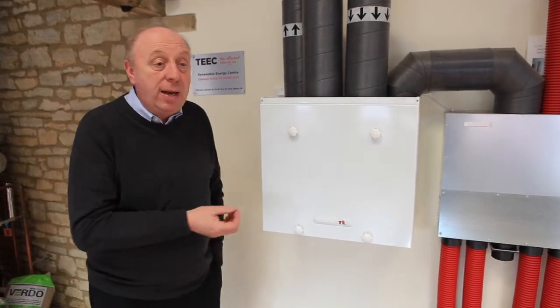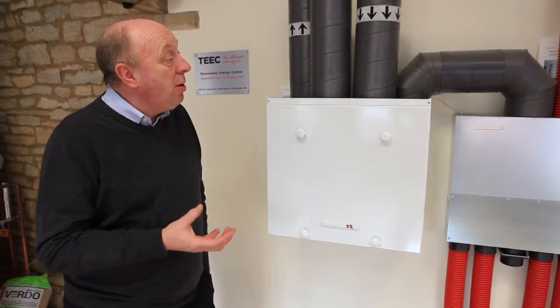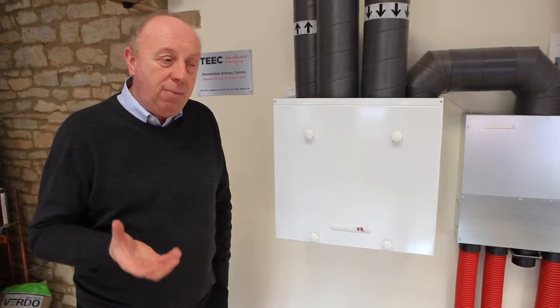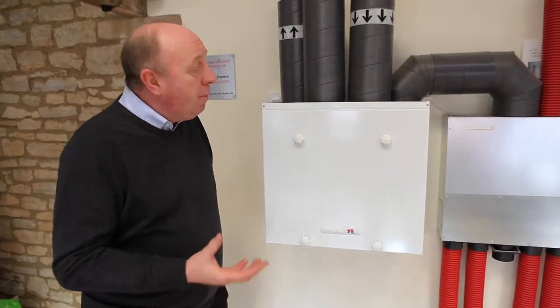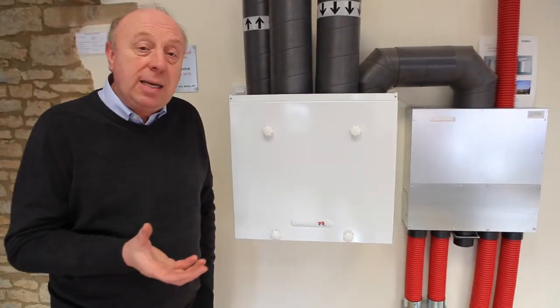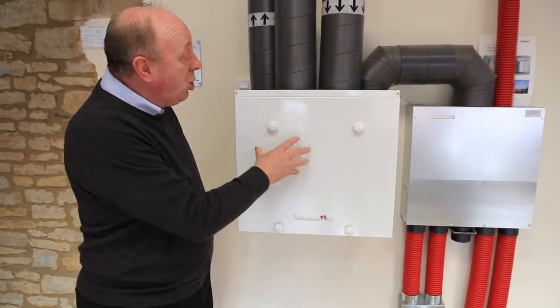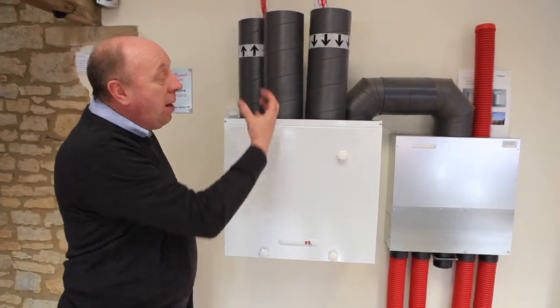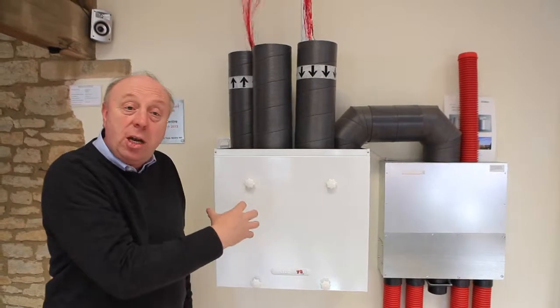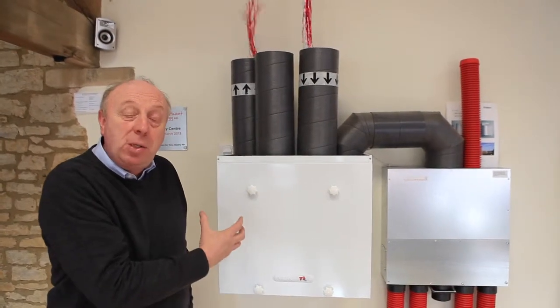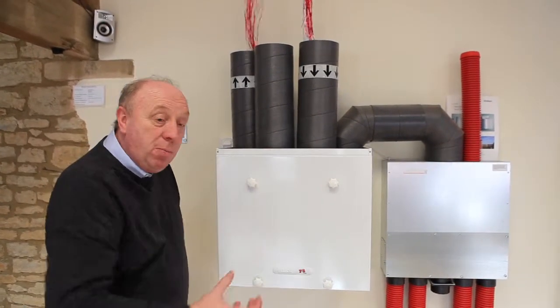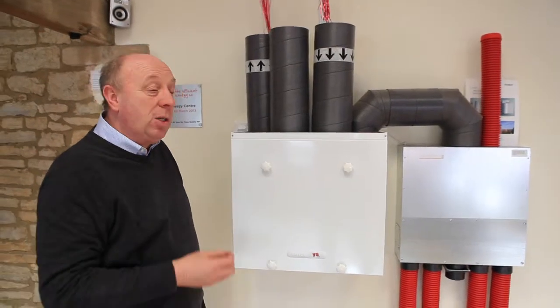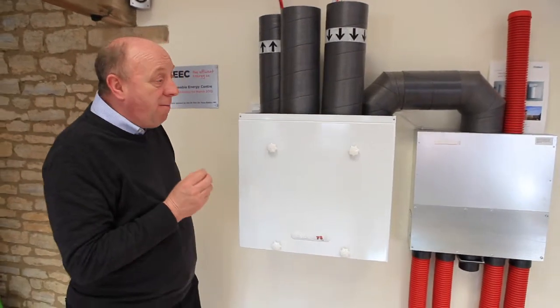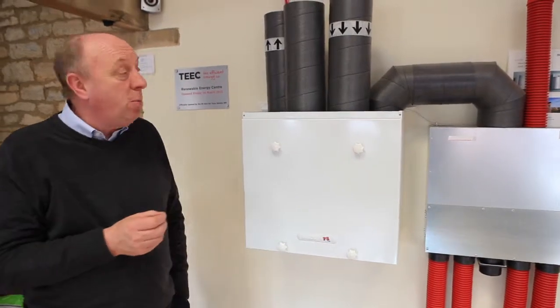So a mechanical vent and heat recovery. This is going to remove stale air from kitchens, bathrooms, toilets, but instead of just dumping all that heat outside, it's going to go over a heat exchanger within this unit, and the cool air coming in is going to go over that heat exchanger and it's going to recover 90% of the heat. So we're going to be moving that warmth back through the buildings, and we see this as becoming a very important part of the renewable trail.